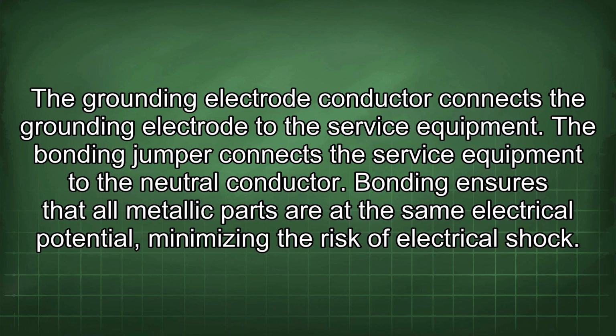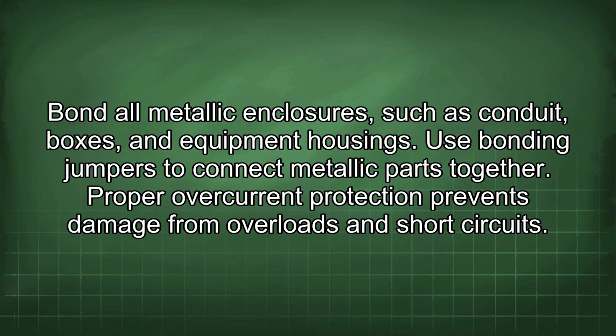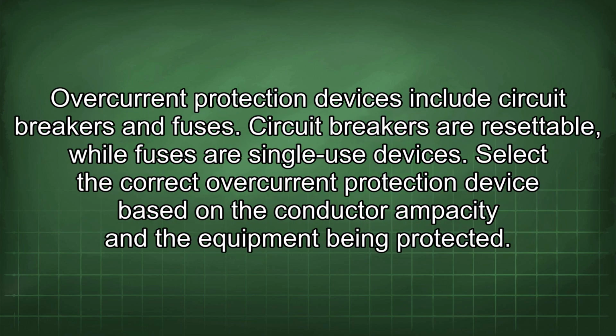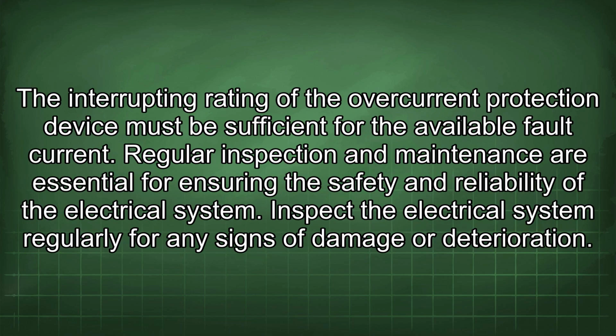Bonding ensures that all metallic parts are at the same electrical potential, minimizing the risk of electrical shock. Bond all metallic enclosures, such as conduit, boxes, and equipment housings. Use bonding jumpers to connect metallic parts together. Proper overcurrent protection prevents damage from overloads and short circuits. Overcurrent protection devices include circuit breakers and fuses. Circuit breakers are resettable, while fuses are single-use devices. Select the correct overcurrent protection device based on the conductor ampacity and the equipment being protected. The interrupting rating of the overcurrent protection device must be sufficient for the available fault current.